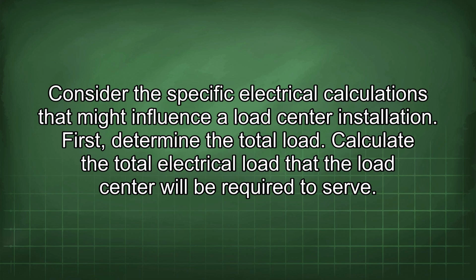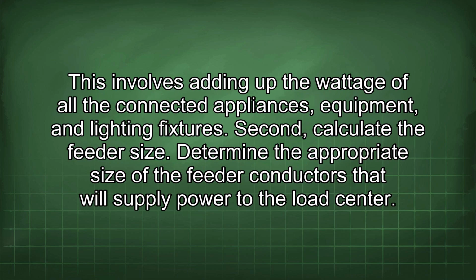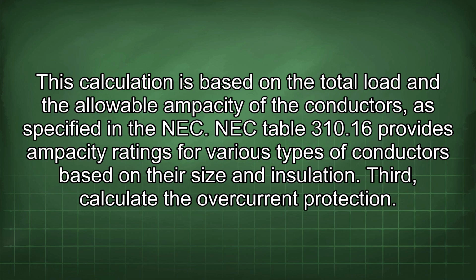Consider the specific electrical calculations that might influence a load center installation. First, determine the total load. Calculate the total electrical load that the load center will be required to serve. This involves adding up the wattage of all the connected appliances, equipment, and lighting fixtures. Second, calculate the feeder size. Determine the appropriate size of the feeder conductors that will supply power to the load center. This calculation is based on the total load and the allowable ampacity of the conductors, as specified in the NEC. NEC Table 310.16 provides ampacity ratings for various types of conductors based on their size and insulation.